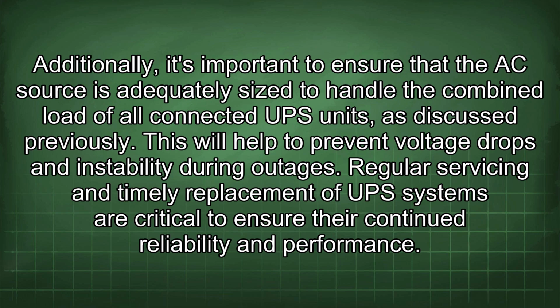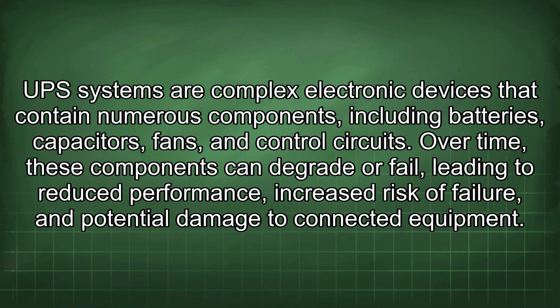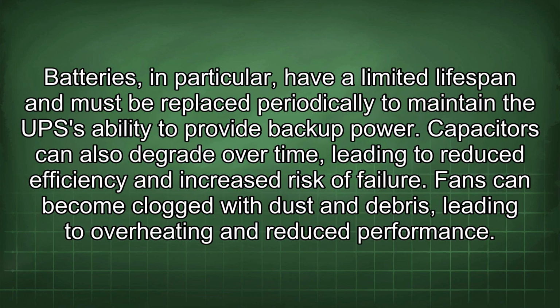Regular servicing and timely replacement of UPS systems are critical to ensure their continued reliability and performance. UPS systems are complex electronic devices that contain numerous components, including batteries, capacitors, fans, and control circuits. Over time, these components can degrade or fail, leading to reduced performance, increased risk of failure, and potential damage to connected equipment. Batteries, in particular, have a limited lifespan and must be replaced periodically to maintain the UPS ability to provide backup power. Capacitors can also degrade over time, leading to reduced efficiency and increased risk of failure. Fans can become clogged with dust and debris, leading to overheating and reduced performance.